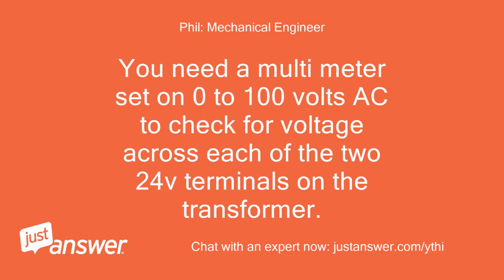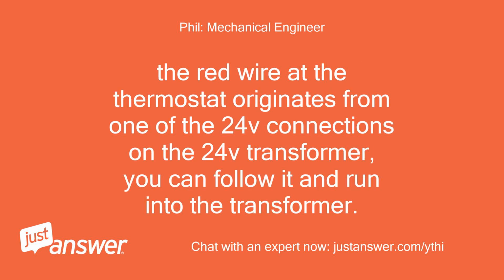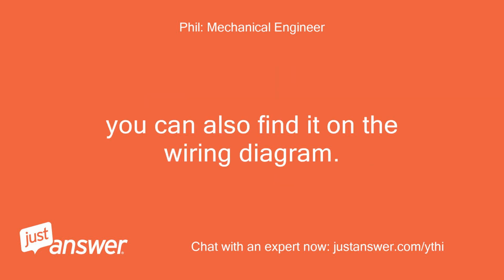You need a multimeter set on 0 to 100 volts AC to check for voltage across each of the two 24V terminals on the transformer. The red wire at the thermostat originates from one of the 24V connections on the 24V transformer. You can follow it and run into the transformer. You can also find it on the wiring diagram.